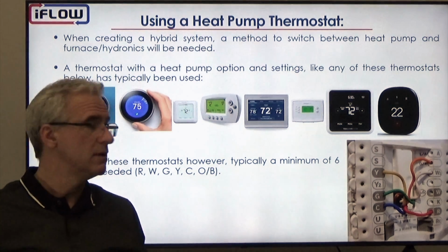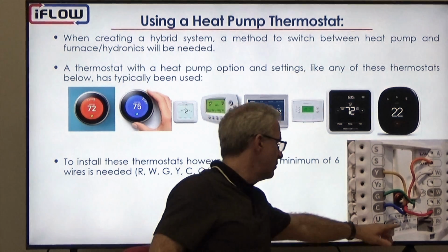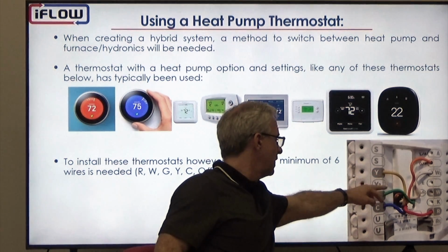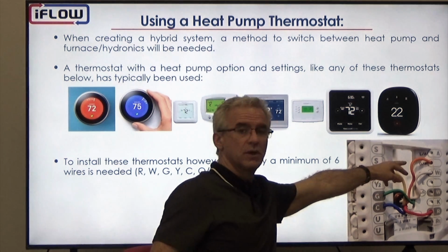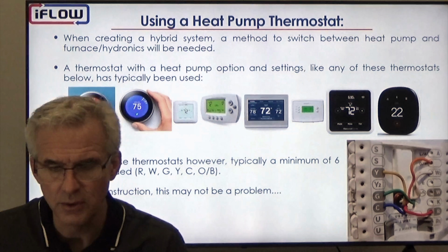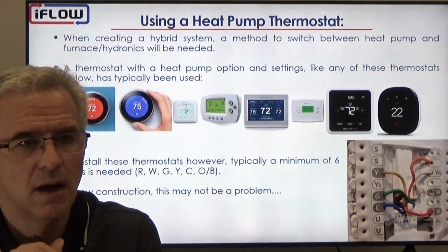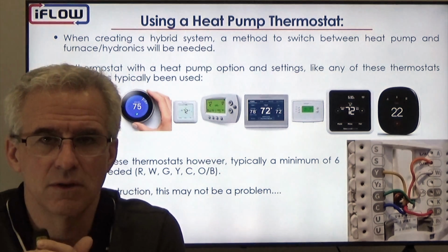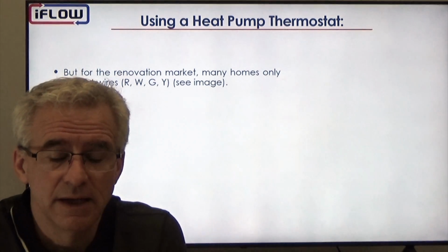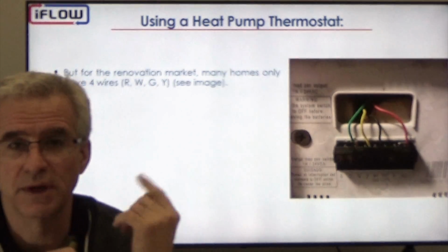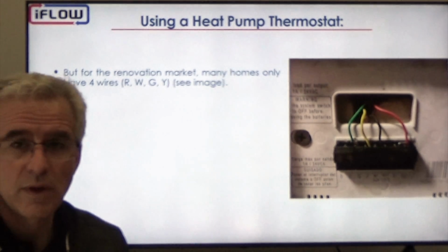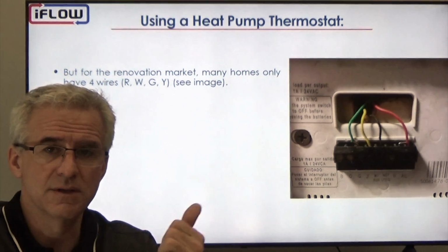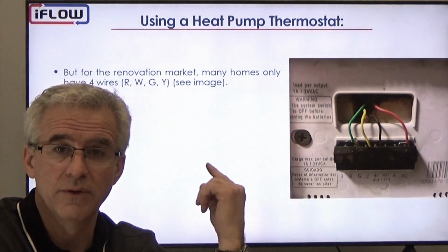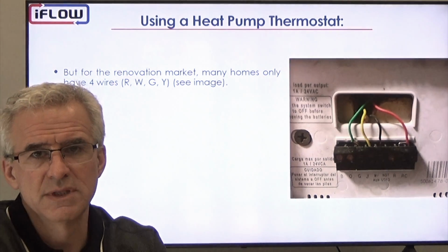If you see this diagram, this picture of the thermostat, typically you would have an R, a W, a Y, and a G. Now we need a C, and we also need a B wire. So in new construction, that's not a problem. You can plan for that and make sure you've got enough wires in the wall. So no issue there. But on the renovation side, many homes only have 4 wires, right? They'll have R, W, G, and Y as depicted in that picture. So in a retrofit, if you now need 6 wires, you need a C wire and a B wire in addition to the 4 that you have. How are you going to install that new thermostat?